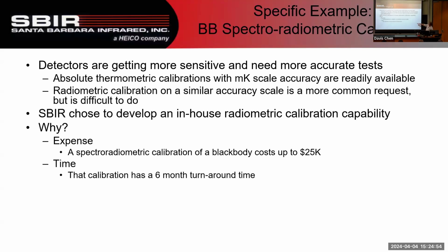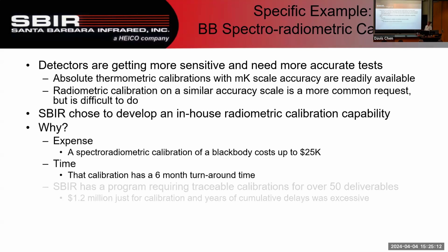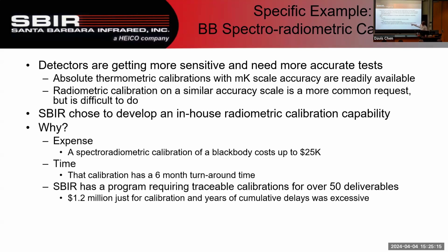If I send my black body off to NIST to get a spectroradiometric calibration, it costs $25,000 to get a piece of paper that gives me a radiometric calibration to plus or minus about 1%. And it takes them about 6 months to turn it around. We have a program that requires 50 deliverables be calibrated. 50 deliverables at $25,000 is $1.2 million just for calibration, and years of cumulative delay if I had to send those things off one at a time. Oh my goodness, it would take forever. We'd never get them back. And there's no way my company is paying $1.2 million for calibration. So we figured out a way to do it ourselves.